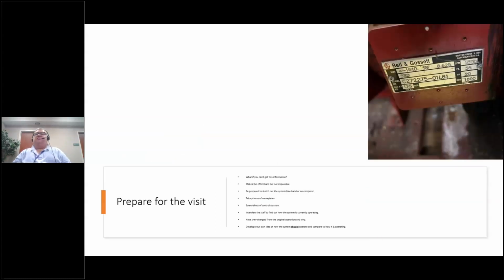If you take a picture of a nameplate on a pump, you get great information. In this case, this pump has the horsepower, feet, and GPM clearly identified. If you wanted a pump curve, this is where you'd find that information - you could send it to the manufacturer, or even get a pump curve from the vendor who sold the pump to the job, and they'd pull that curve and send it to me. This thing is a wealth of information.